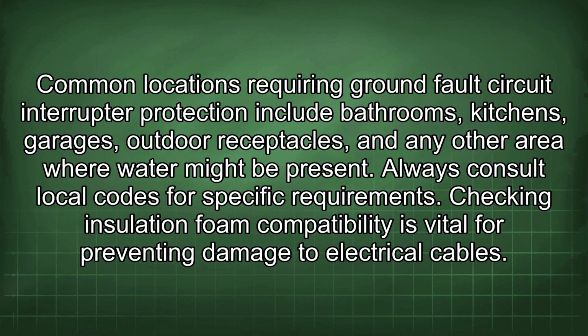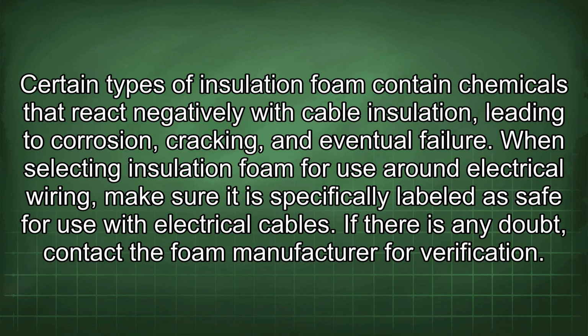Checking insulation foam compatibility is vital for preventing damage to electrical cables. Certain types of insulation foam contain chemicals that react negatively with cable insulation, leading to corrosion, cracking, and eventual failure. When selecting insulation foam for use around electrical wiring, make sure it is specifically labeled as safe for use with electrical cables. If there is any doubt, contact the foam manufacturer for verification.